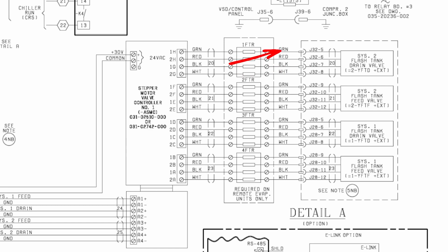With a stepper motor, we energize one coil, we take one step. We energize the other coil, we take another step. We just continue to step through to open and close. We change direction of rotation by changing polarity, and we can do that with these systems. So when we have positive polarity, flowing positive through the green wire and coming back out the red, we rotate clockwise one step. Then positive through the black and coming back on the white, we rotate one more step.